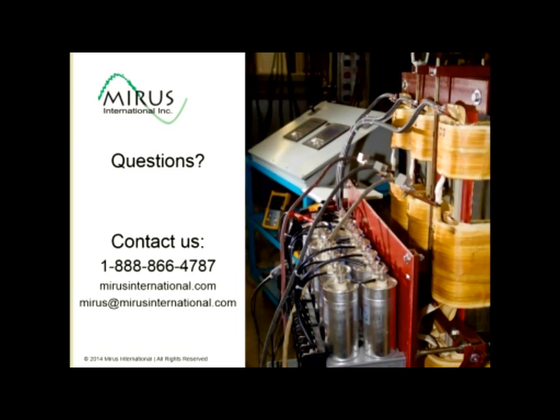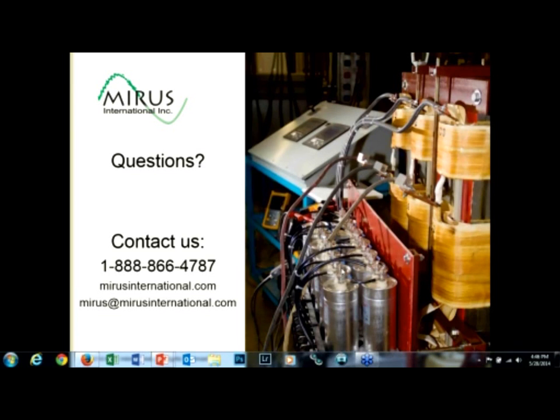Some other questions are asking if we've had any problems with applications involving generators and lineators. And actually, provided the total lineator load connected to the generator does not exceed the generator's full load rating, we have not had generator problems. There have been incidences where they've had a much higher connected load with all filters on it, and then we've gotten close to exceeding the generator's capability curves. But those are very rare, and certainly when it's properly loaded, it's never been a problem.